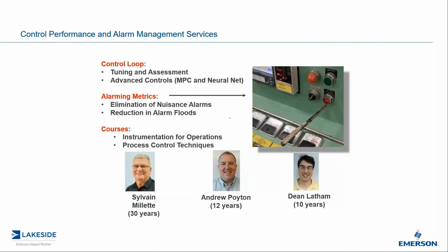Any one of you might go to your control room and look at your alarm banner - I bet it's probably full. I was just reading that over 80% of the alarms generated by control systems are probably what we call noise or nuisance alarms. What we do is develop an alarm philosophy document and perform in-depth alarm analysis to make the alarms relevant - we don't want to eliminate them, we want to make them relevant.